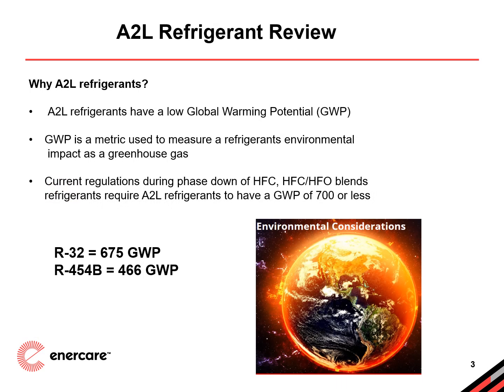A2L refrigerants, an important topic shaping the future of our industry. These refrigerants are key because they have a low global warming potential, or GWP. GWP measures how much a refrigerant contributes to global warming, and the lower the number, the better it is for the environment. With regulations phasing down traditional HFC refrigerants, the industry is shifting towards A2Ls that meet the new requirement of a GWP of 700 or less. For example, R32 has a GWP of 675, while R454B is even lower at 466.